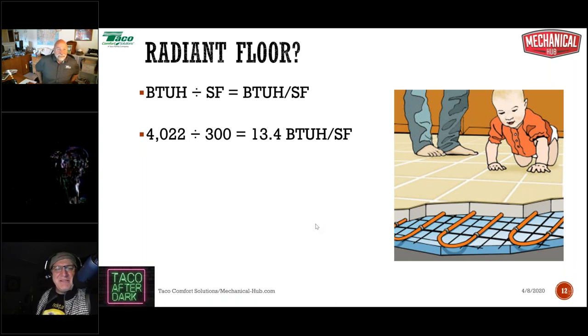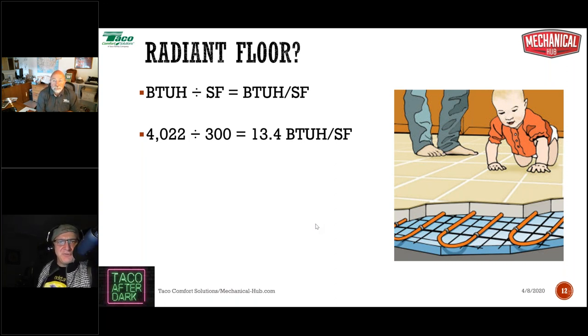Yeah. The temperature should be the same. The surface temperature should be the same for either finished floor material. Think about this. If you need a 75 degree floor surface temperature to heat a room, a 75 degree carpet surface temperature and a 75 degree tile surface temperature are both 75, right? It's the same. A tile 75 isn't cooler than a carpet 75.